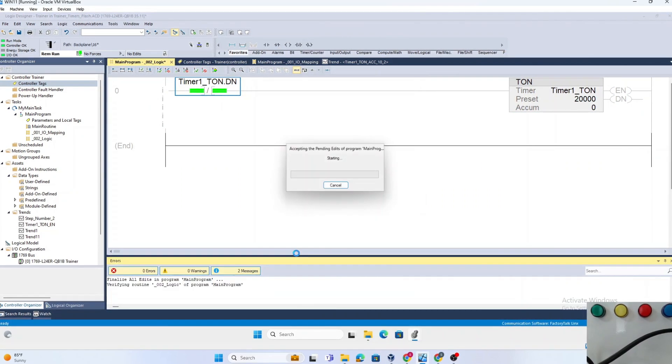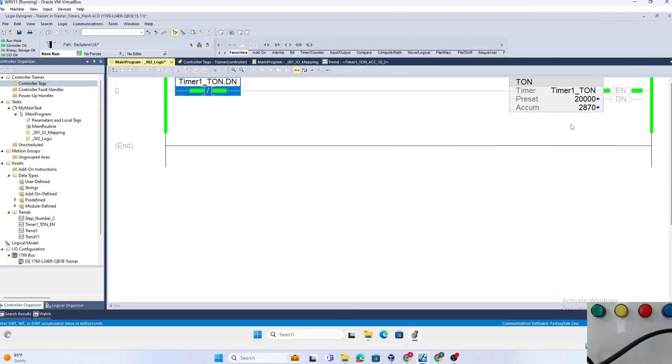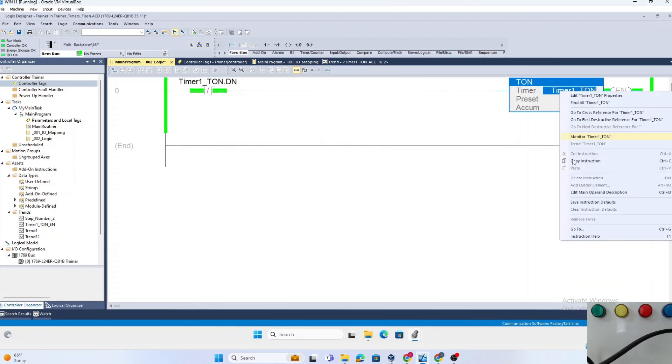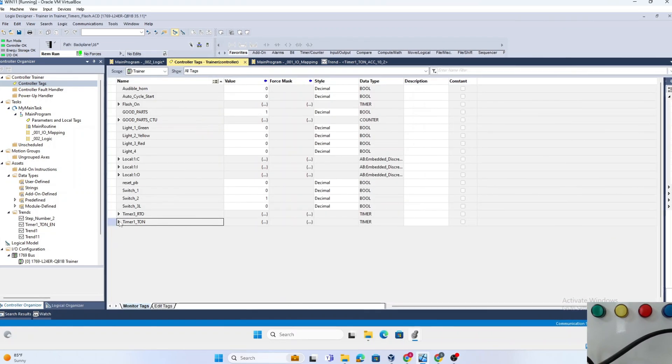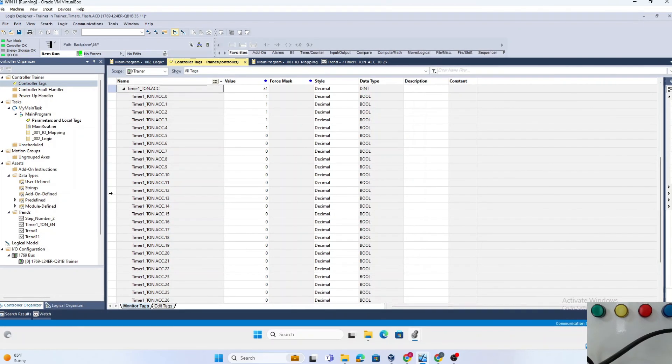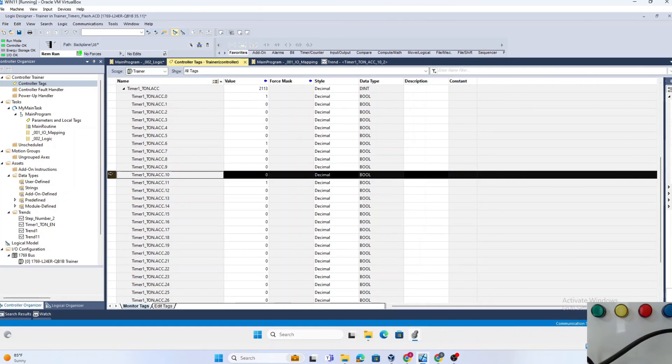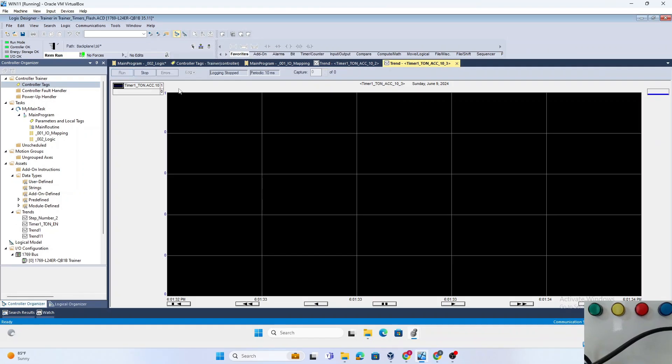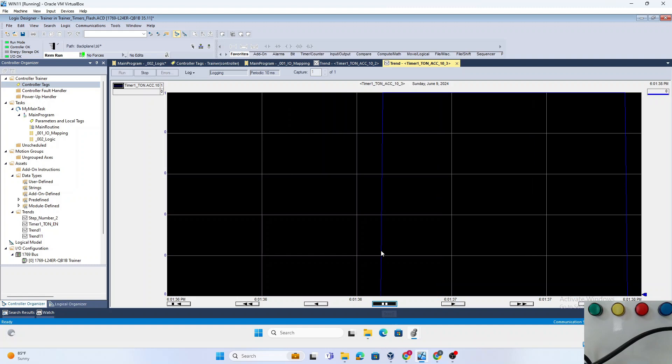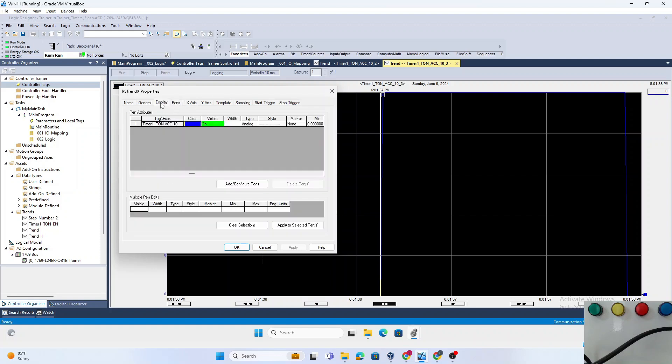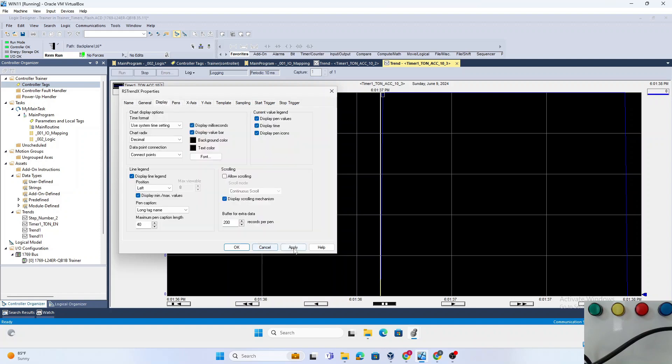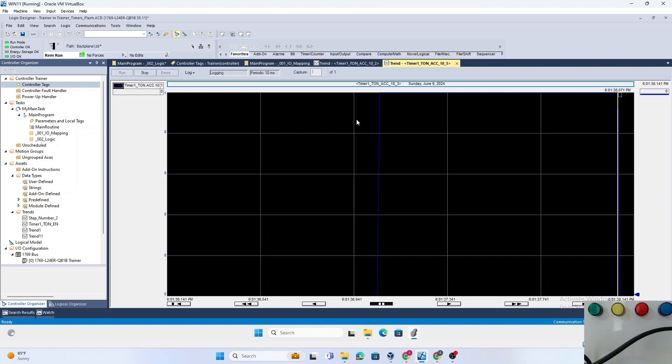Now if we monitor the timer instruction, it has an accumulator word which you can see is changing in milliseconds. If you expand this accumulator value and monitor bit number 10, and let's use a trend here. If you look at the time between when that bit went high, at 37,041 to 38,071, that's about 1024 milliseconds. That's 2 to the power of 10, which equals 1024 milliseconds.